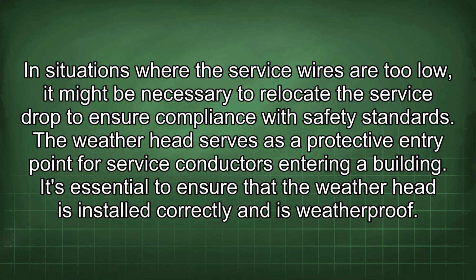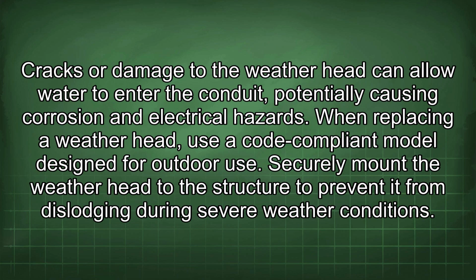It's essential to ensure that the weatherhead is installed correctly and is weatherproof. Cracks or damage to the weatherhead can allow water to enter the conduit, potentially causing corrosion and electrical hazards. When replacing a weatherhead, use a code-compliant model designed for outdoor use. Securely mount the weatherhead to the structure to prevent it from dislodging during severe weather conditions.